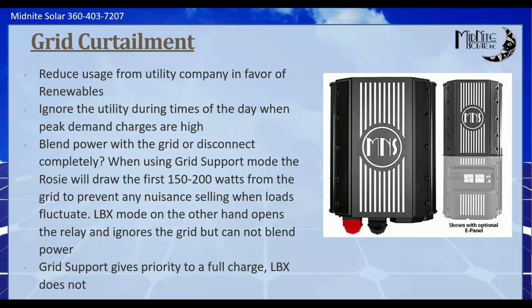Grid support gives priority to a full charge where LBX does not, and I'll go into much greater detail on that when we get to those modes. But that is something that can be important if you're using a lead acid battery versus a lithium battery. We may need to treat them slightly different.